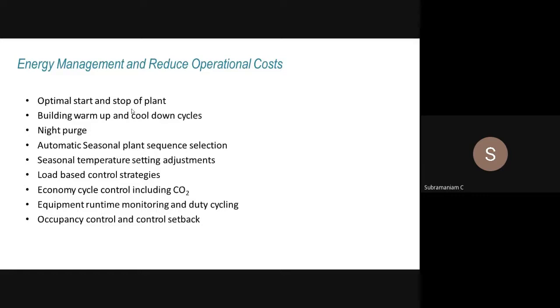Optimal start-stop of the building, building warm-up and cool-down cycle. We will know, and we can better manage the building. If it is a hospital or a hotel, these will all be very important. Seasonal temperature adjustment, economy cycle, equipment runtime. For maintenance purposes, if there are 5 chillers, we can run them in such a way that all are run equally.